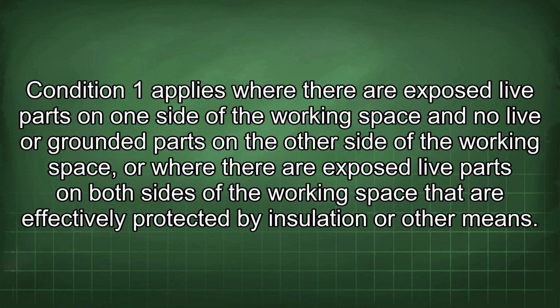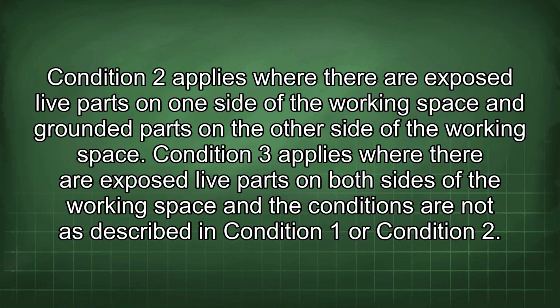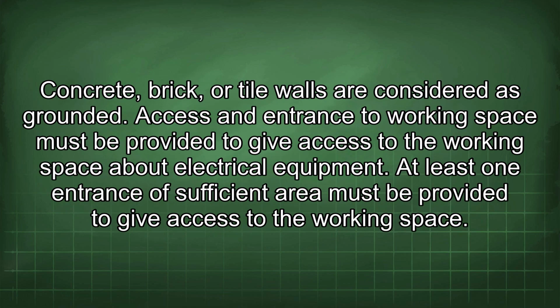Condition 1 applies where there are exposed live parts on one side of the working space and no live or grounded parts on the other side of the working space, or where there are exposed live parts on both sides of the working space that are effectively protected by insulation or other means. Condition 2 applies where there are exposed live parts on one side of the working space and grounded parts on the other side of the working space. Condition 3 applies where there are exposed live parts on both sides of the working space and the conditions are not as described in Condition 1 or Condition 2. Concrete, brick, or tile walls are considered as grounded.